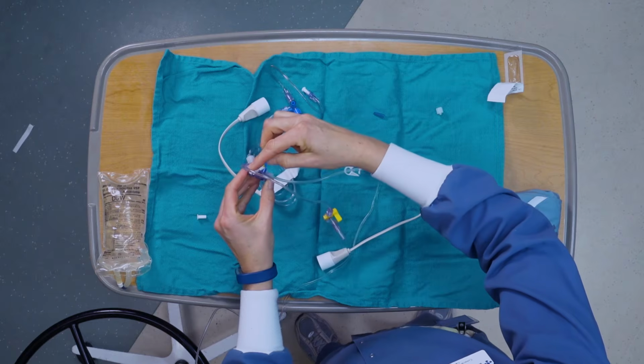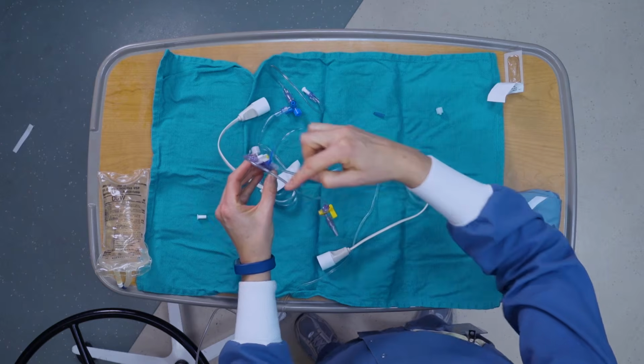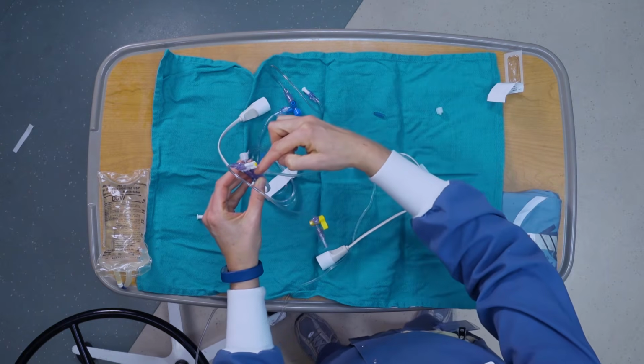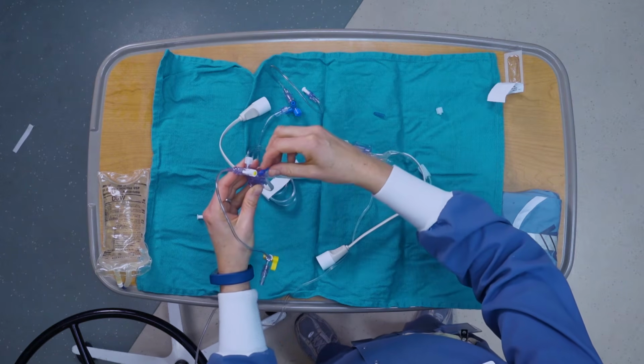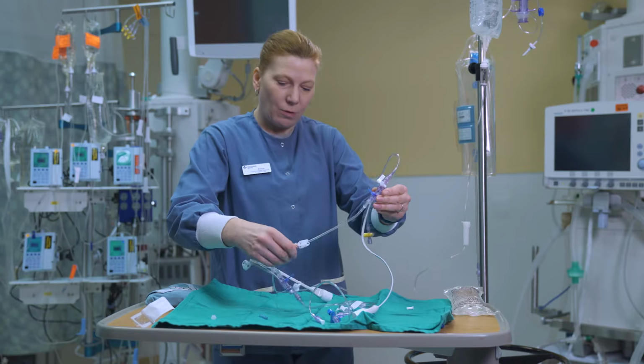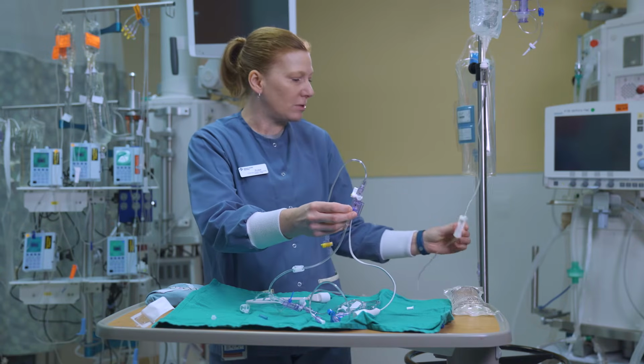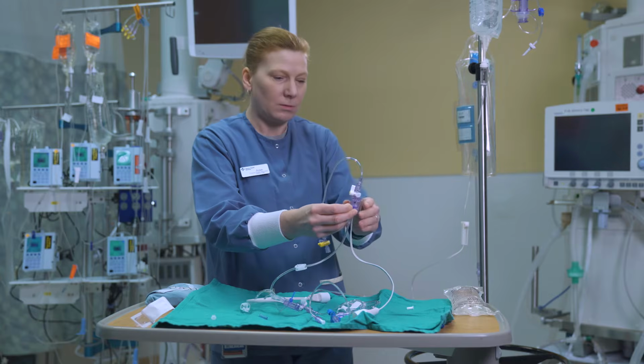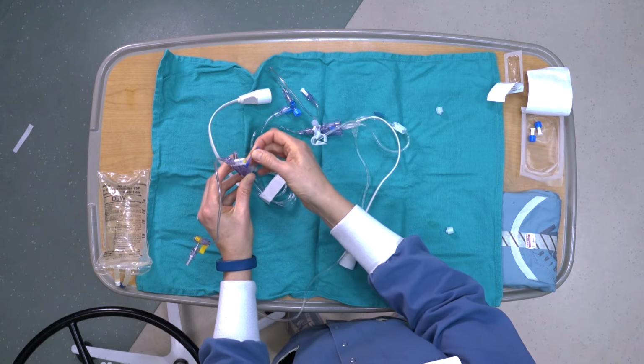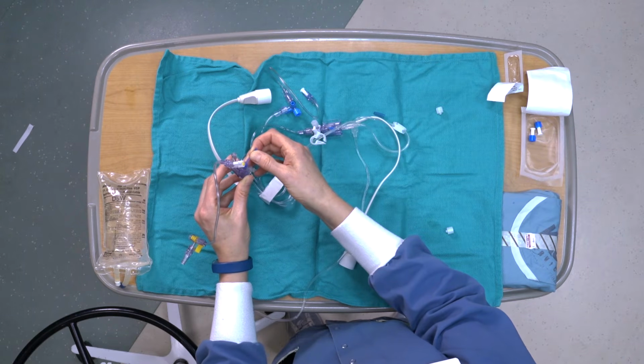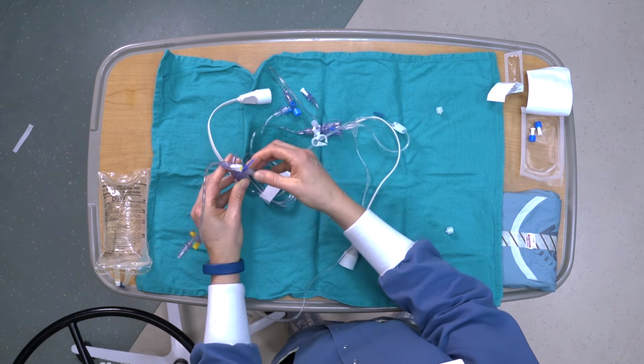I'm going to turn the transducer so that it's off to where it would be attached to the patient, but it is open to the transducer. Okay, and then in order to get this moving appropriately, we need to pull that pigtail. So I'm just going to make sure I haven't got anything clamped here. I'm going to pull my pigtail, and you're going to see the fluid move through there, and that means that you've flushed it through.